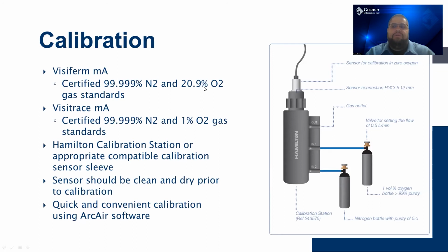And why you need 2 different gas standards is that when you're calibrating these sensors, you're using a low point near 0 and a high point at the 20.9% mark. Why it's important to use a certified 20.9% oxygen is you're telling the sensor that this is how much oxygen is in the environment, and I want you to set yourself at this point. So if you were to calibrate in air, for example, or using an air compressor, depending on your elevation or how much moisture is in the air, you can set the sensor at a bad spot, just because moisture will reduce the amount of O2 in the environment. So really dried certified air is the best way to go when you're setting the high point for the Visiferm mA.